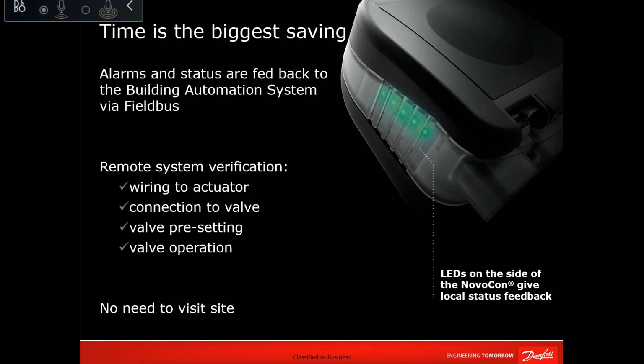So the L and XL application is specifically for district cooling, because in district cooling ETS rooms, you might not need a PLC anymore, I would say, because built into the actuator, you have the ready program and sequence of operation to open and close your valve based on a temperature. So for the remaining alarms that you need, let's say the DP transmitter across the strainer, which will show you if the strainer is blocked or not, this is one wire which can be linked to the Novocon and remotely sent to the main plant.